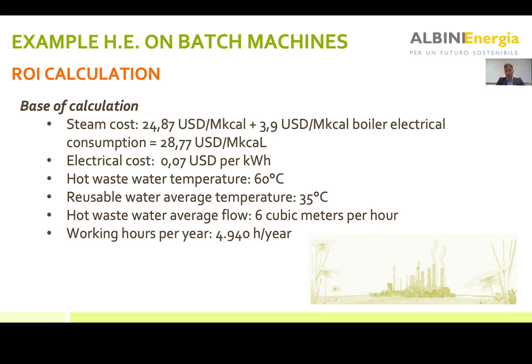You must consider that in this situation, the boiler was used to warm up the temperature of the thermal oil, and the thermal oil was the fluid designed to warm the temperature of the water in the washing machine. So if you use thermal oil, you must consider also the power of the pumps and the power of all the auxiliary equipment you need to treat the exhaust of the boilers. We made the calculation according to the real consumption and arrived at 3.9 US dollars per megacalorie for those items.